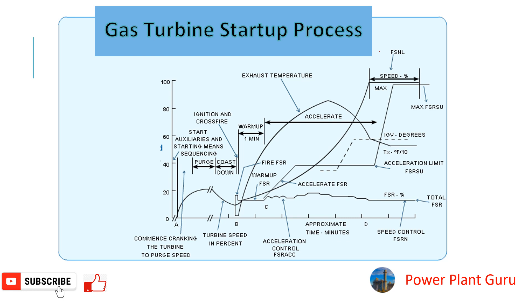This plot is a very complicated one with different important things to note. Looking at the Y-axis, we can see it goes from 0 to 100, denoting the speed of the turbine in percentage — from zero percent to full speed, which is 100%, called the full speed no-load condition. There is also a line showing how your turbine speed is increasing, with different breakup points where the time delay is more.